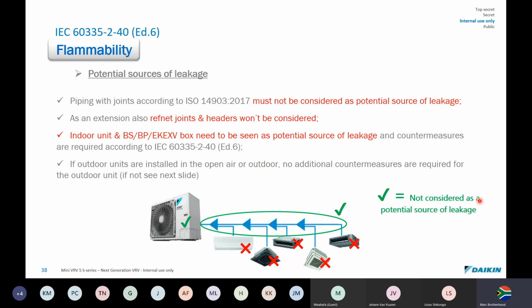I've put here a tick. Even your outdoor units are not considered a source of leak, because this has primarily got to do with leakage where people can be staying. So if these BS boxes are in a ceiling, in a passage, and there's a leak, there's a low possibility, because of supply air and extract air, that the leak will just get sucked out. It's not always the case in a hotel room. So they have classed indoor units as your risks. And they've said this is where the leaks are possible and where you can get flame propagation.